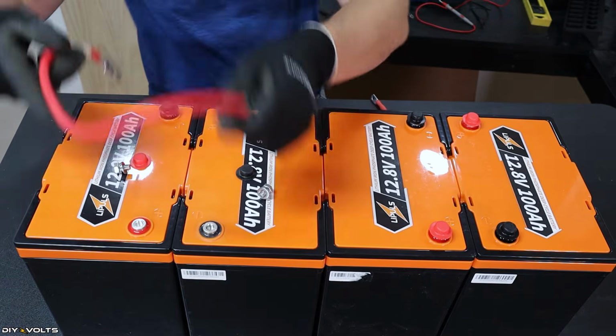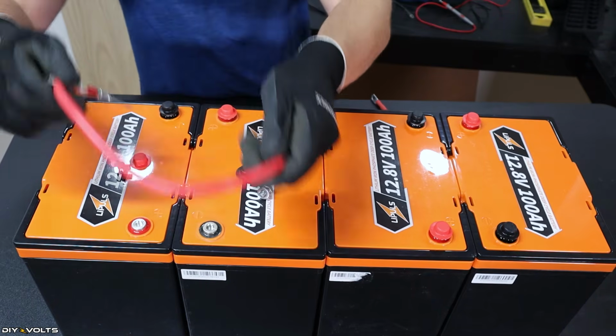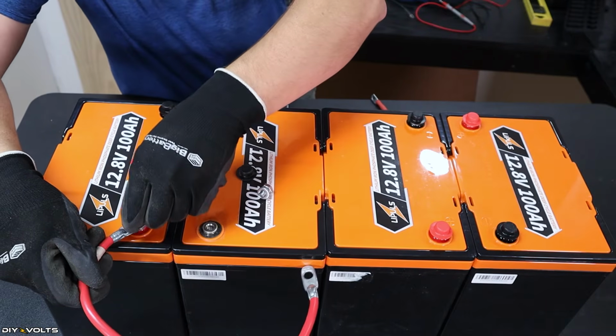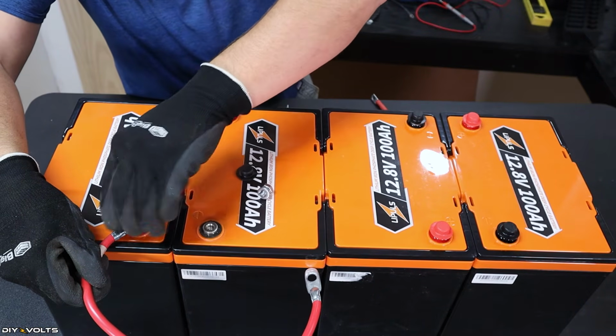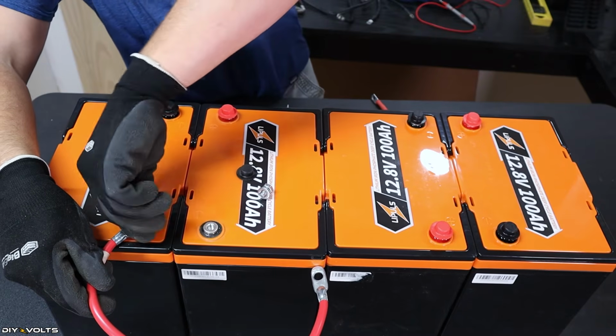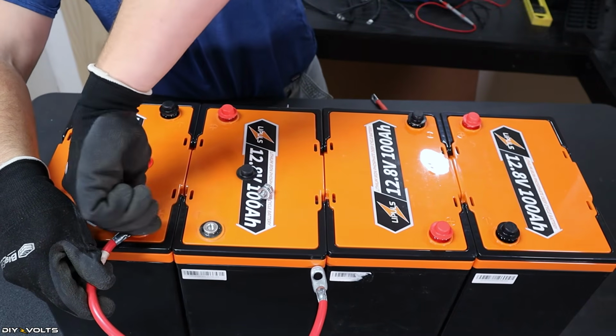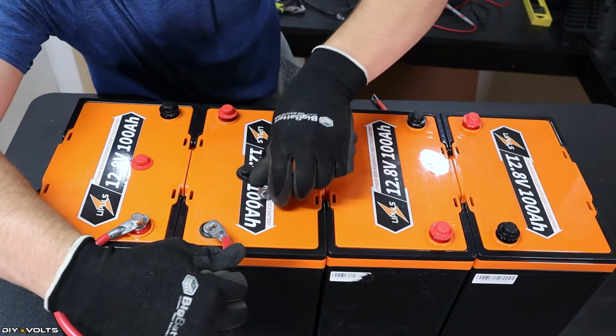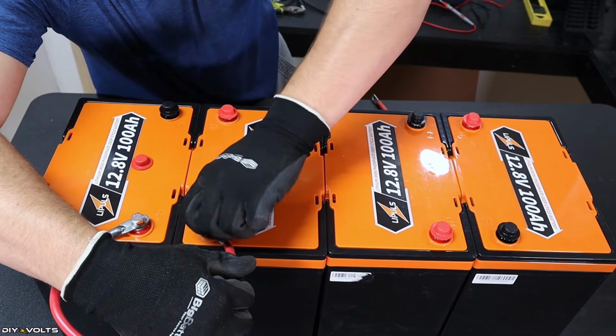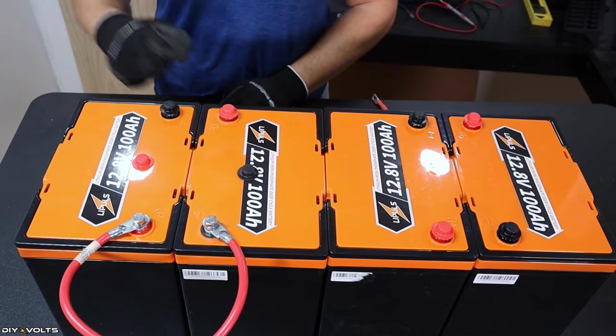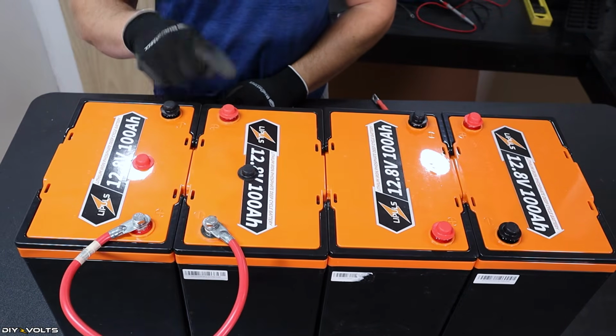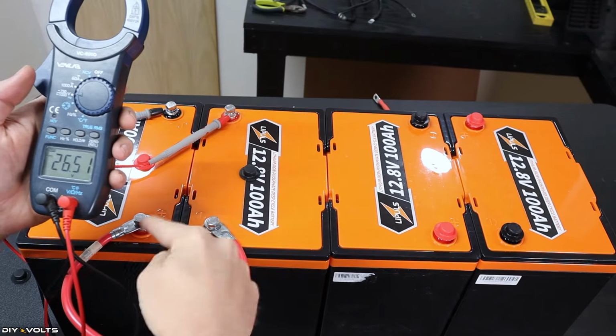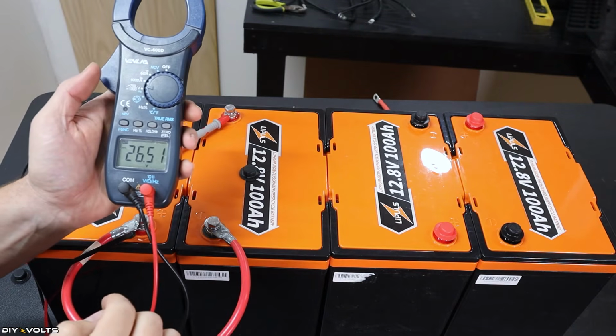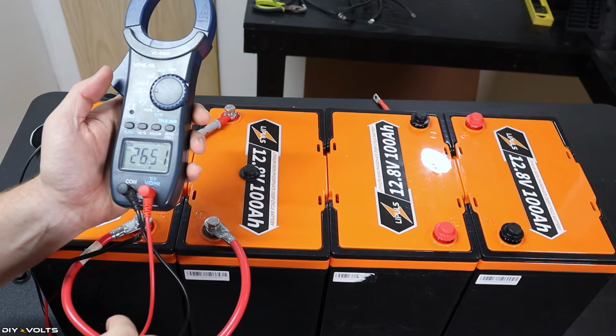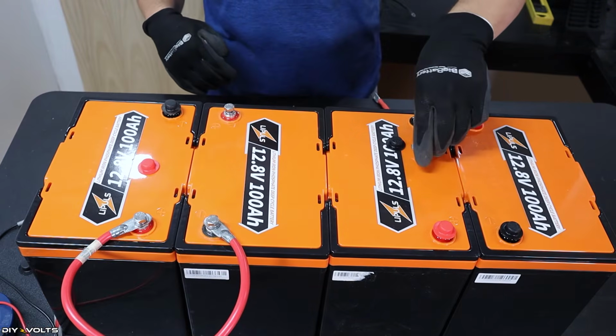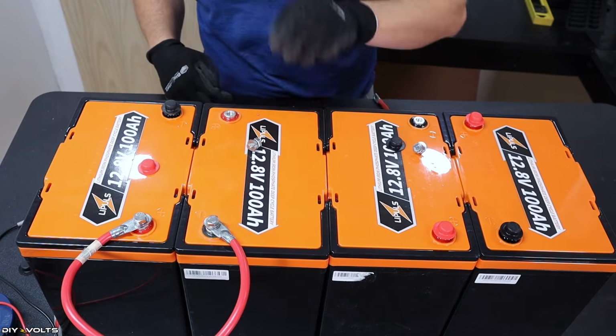Now, of course, you want to make sure that you have your cables sized correctly. In this case, I am simply doing this for demonstration purposes, so my cables are too long and they may not be the correct gauge for sending this amount of amperage through them. If we were to test between this point and this point, we should see 24 volts. Each battery is 13.25 volts, so we have 26.51 volts. That is correct. I'm going to connect these positive and negative together over here.